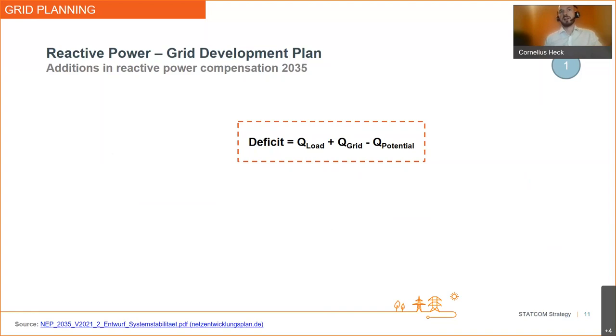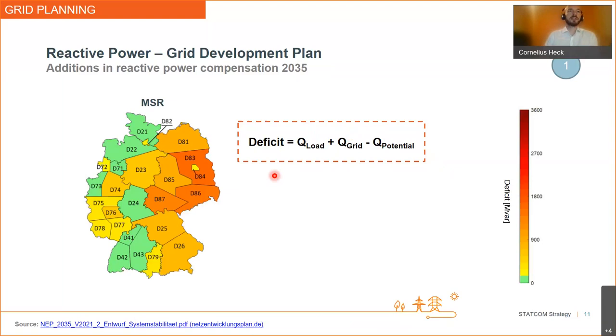We're just calculating a load flow, and we calculated how much reactive power our loads will need, how much reactive power in each operation scenario our grid will need, so how much Q is lost in our transformers and our lines, and then we will subtract the Q potential coming from our generation units and the compensation assets that we have already in place. And we sum up this term, and we do that for the grid areas that you can see on the left side.